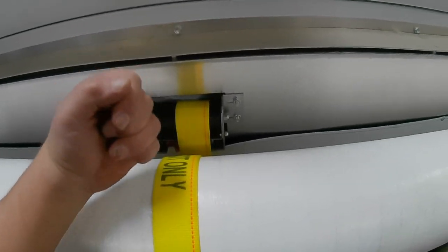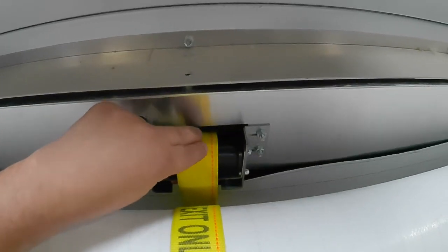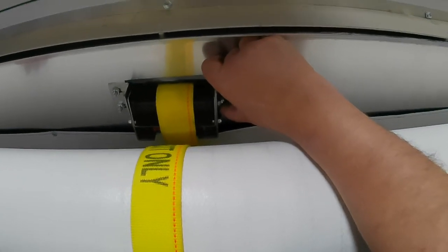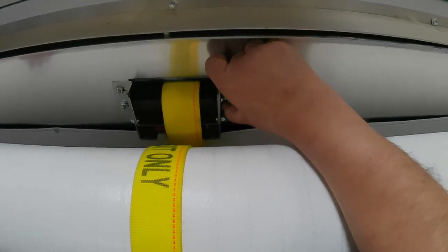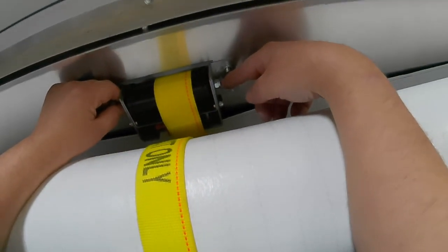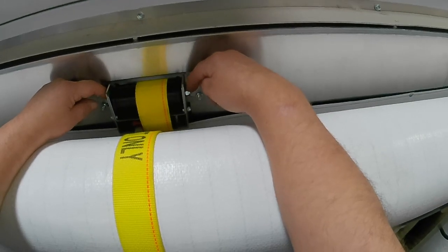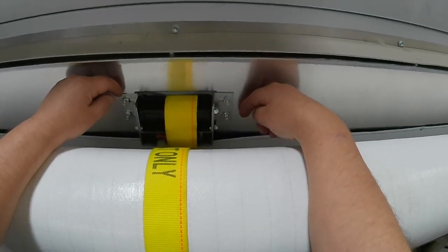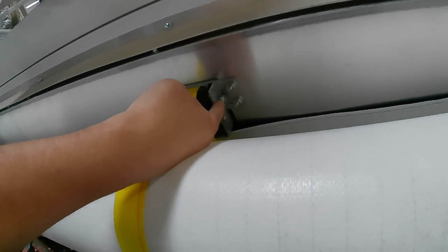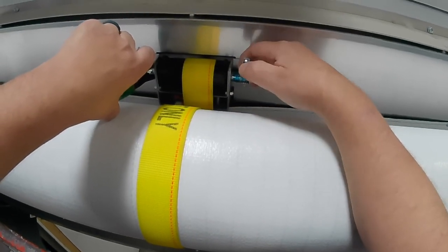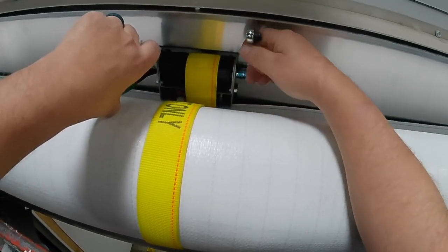So that is our switch right there, and this little hub, which pulled down for whatever reason, this little hub got stuck in the downward position, and all you had to do is, that's it. So I am wondering if I take a little bit more tension off of this nut right here. So yeah, let me take a little bit of tension off of this nut, and hopefully this problem will never happen again.